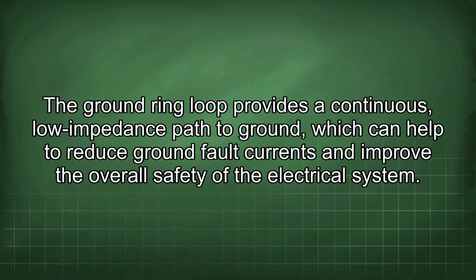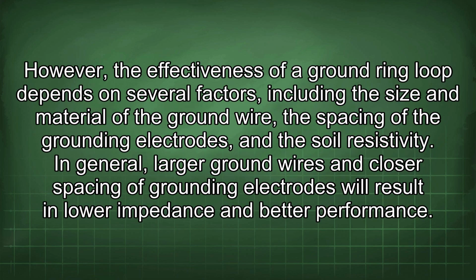The ground ring loop provides a continuous, low-impedance path to ground, which can help to reduce ground fault currents and improve the overall safety of the electrical system. However, the effectiveness of a ground ring loop depends on several factors, including the size and material of the ground wire, the spacing of the grounding electrodes, and the soil resistivity. In general, larger ground wires and closer spacing of grounding electrodes will result in lower impedance and better performance.